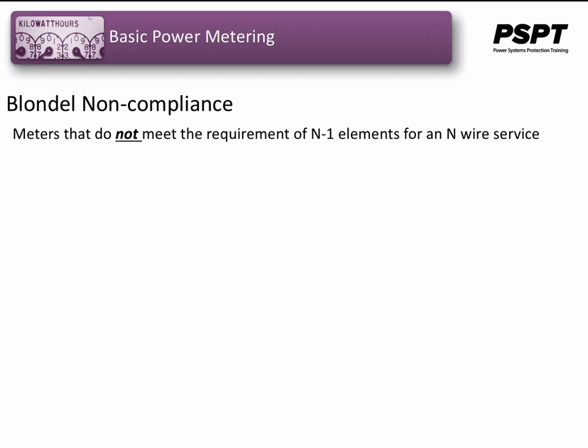When a metering system is non-compliant, that means the meters do not meet the requirement of n-1 elements for an n-wire service. Now, this doesn't mean that the metering is in error, because some of the assumptions that are made are within the accuracy rating that we're looking for. It just means that if the system was pushed, there is a possibility that we would land outside the metering accuracy that would be required. However, there are plenty of meters out there that are non-Blondel compliant, and they were basically put in the system because of economic reasons, as we stated before, where we could reduce the number of elements and reduce the number of PTs and CTs that are connected to the system in order to save money over the long run.